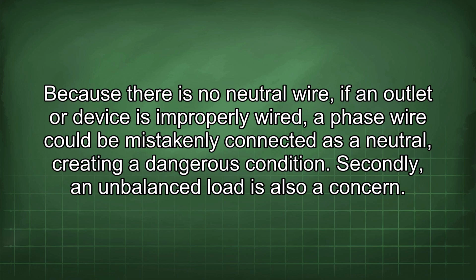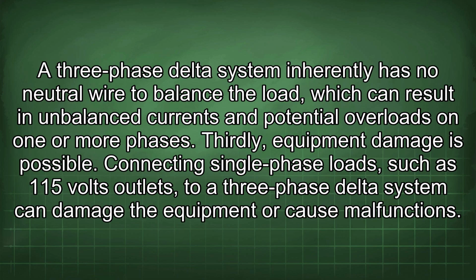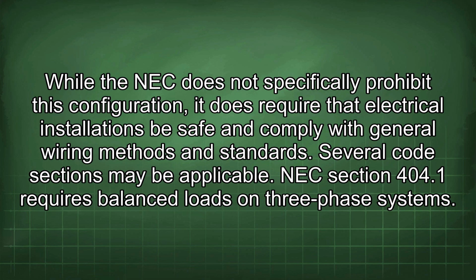Secondly, an unbalanced load is also a concern. A three-phase delta system inherently has no neutral wire to balance the load, which can result in unbalanced currents and potential overloads on one or more phases. Thirdly, equipment damage is possible. Connecting single-phase loads, such as 115-volt outlets, to a three-phase delta system can damage the equipment or cause malfunctions. While the NEC does not specifically prohibit this configuration, it does require that electrical installations be safe and comply with general wiring methods and standards.